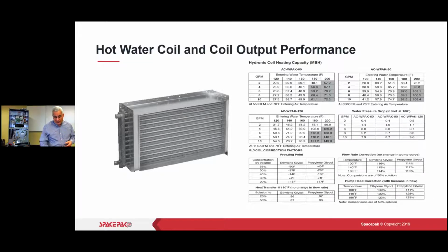It's very important, gentlemen, in anything you're doing in the world of SpacePak or in hydronics or in cooling, block loads just aren't good enough. We do need a room by room, so then we know our total BTUs. This way we can figure out how many outlets we'll need per room, and then if I'm going to size the coil, what size coil I'm going to need and what GPM I'm going to need.